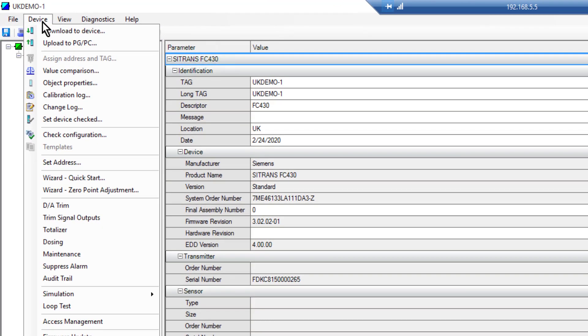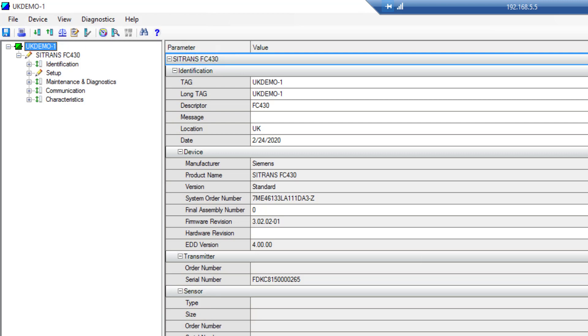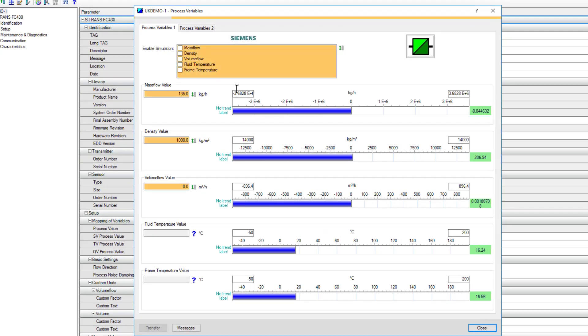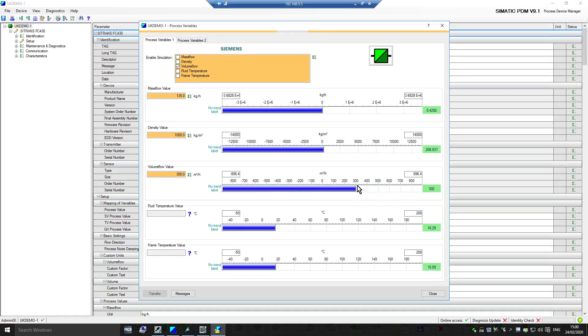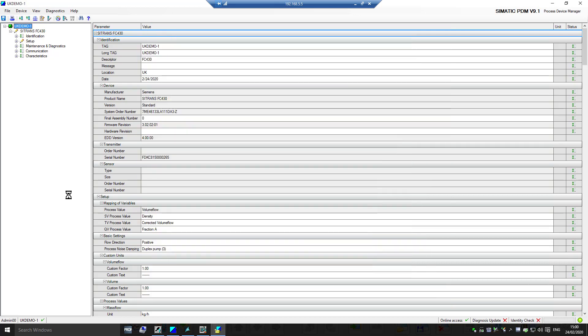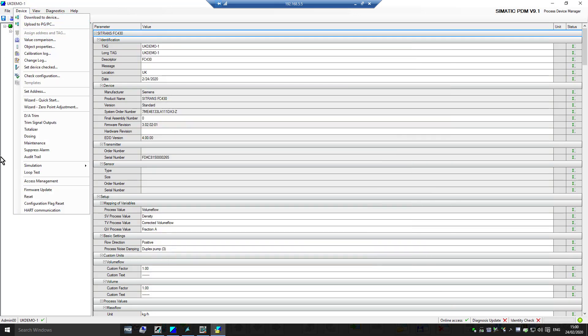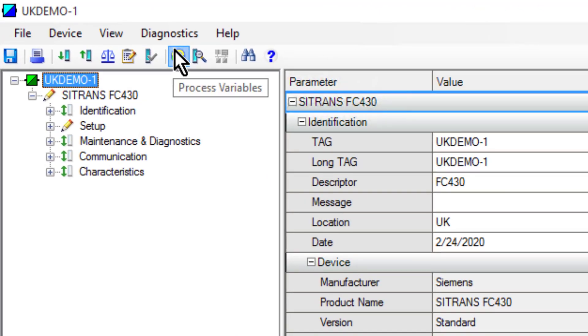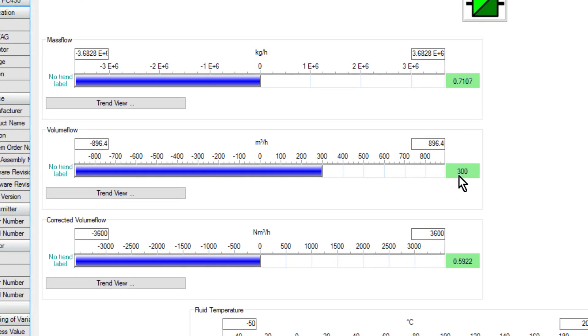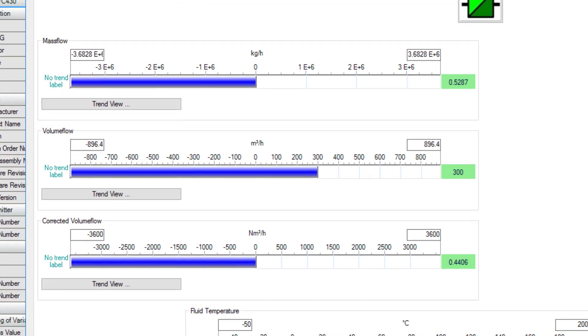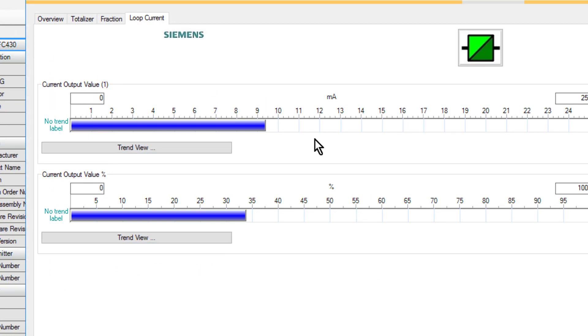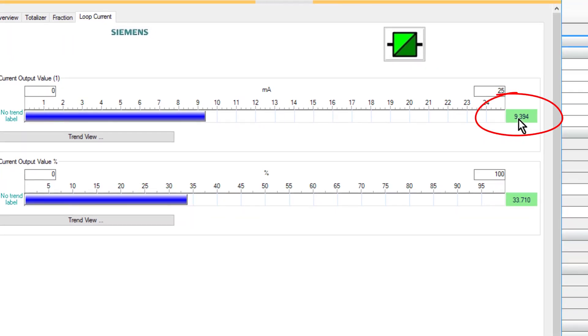So to simulate, we go to device simulation and process values. For this particular one, our main process value on milliamps is volume flow. We'll set that to 300 and transfer that to the instrument. We can see there the simulation, but what that should have done as well is done a full simulation. If I have any pulsed output set for totalizing or anything, those will start counting up. We can check that by clicking the process values. I can see here volume flow is 300, and my current output is 9 milliamps.